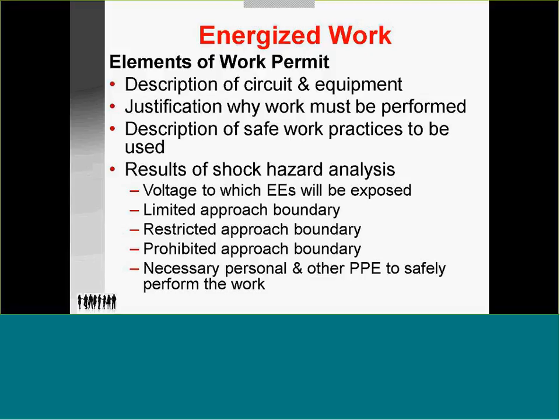It also lists the justification why work must be performed energized. If there is no other way, if it's infeasible to do it de-energized, then it'd be noted. Safe work practices to be used, the left-hand rule, shielding if necessary, and we'll show you a photo of that shortly, and different methods. Then the results of the shock hazard analysis.